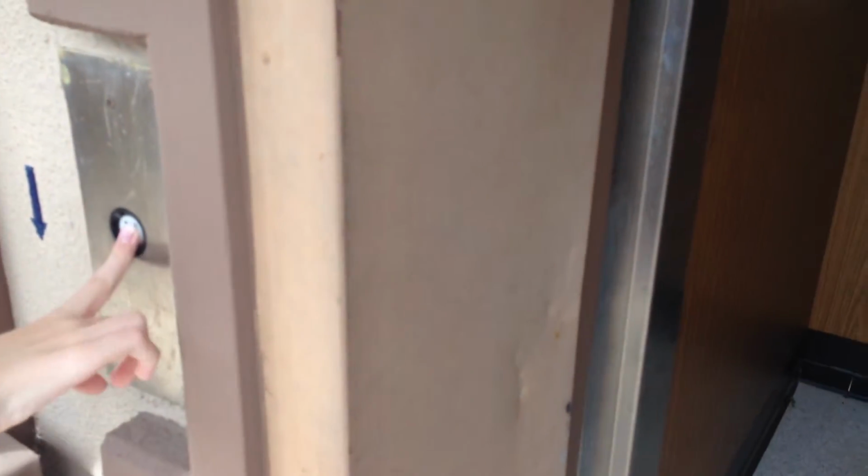Pretty nice. Interesting letter. Yeah. See, the hall station out here is GAL? Yep. GAL hall station. Oops. When it wants to close, it will close. It closes right after I press the button. Yeah. That's maybe a controller failure there. Door tracks are very skinny. Sometimes relay logic elevators are not very patient. Yeah, it's true. Let's go down to one.